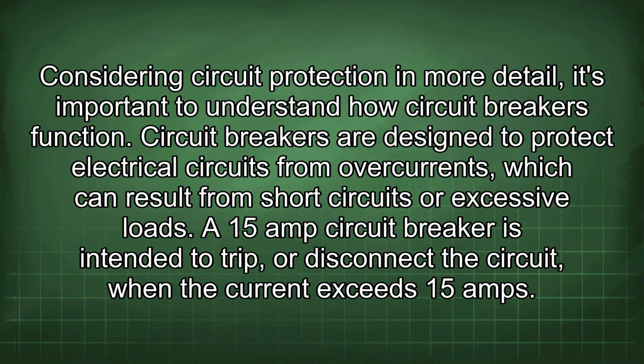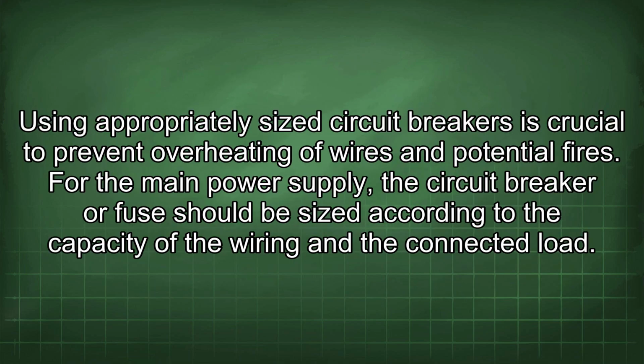Considering circuit protection in more detail, it's important to understand how circuit breakers function. Circuit breakers are designed to protect electrical circuits from overcurrents, which can result from short circuits or excessive loads. A 15-amp circuit breaker is intended to trip or disconnect the circuit when the current exceeds 15 amps. Using appropriately sized circuit breakers is crucial to prevent overheating of wires and potential fires.